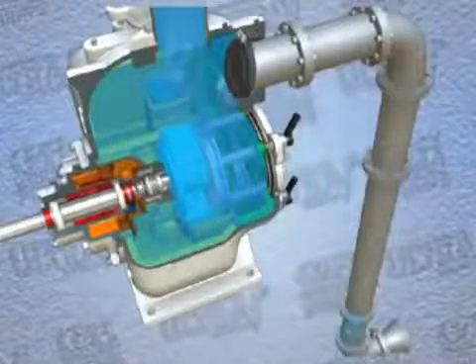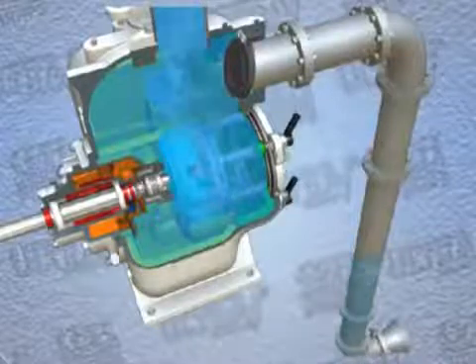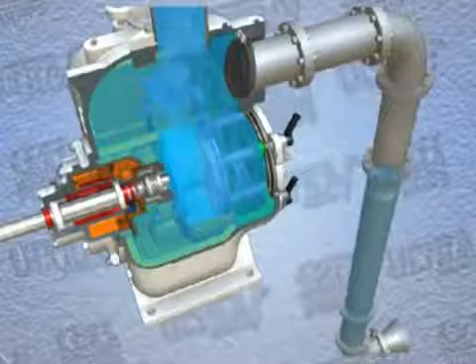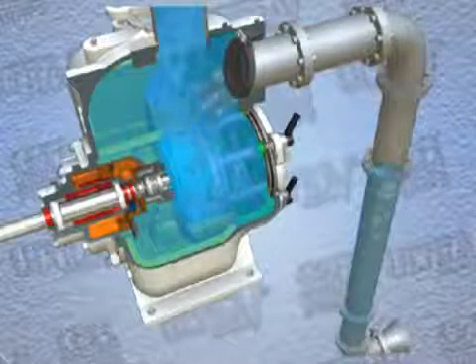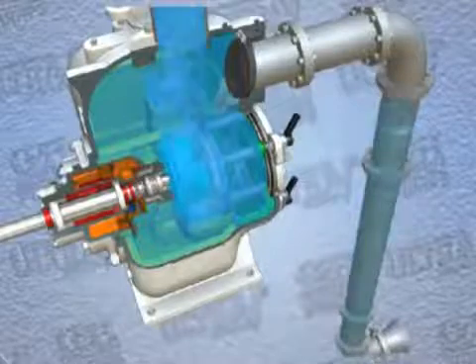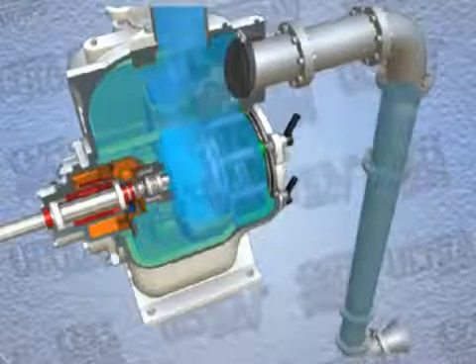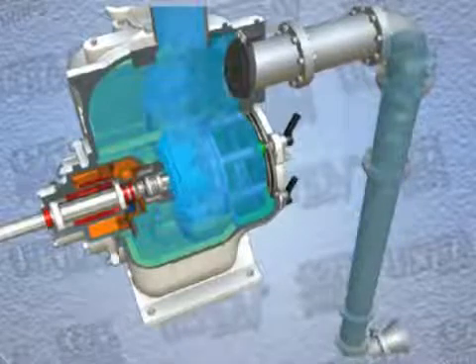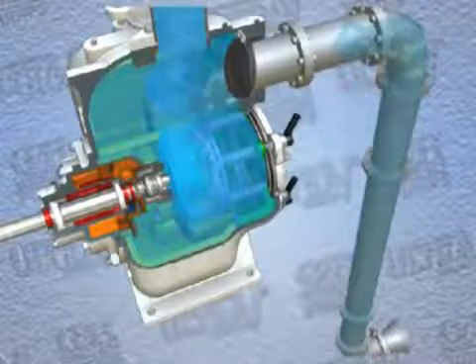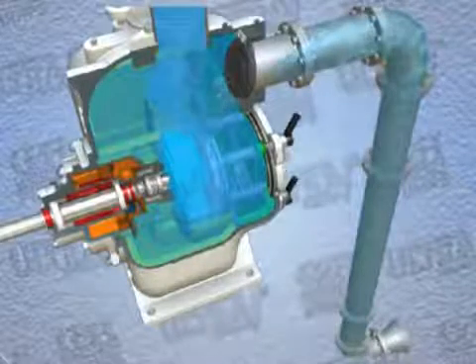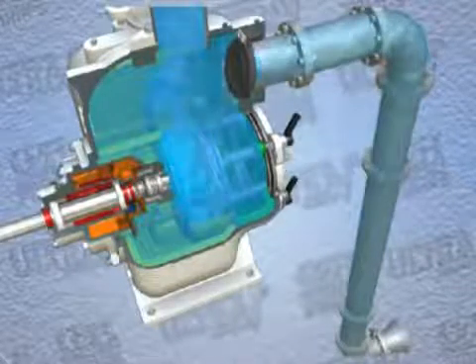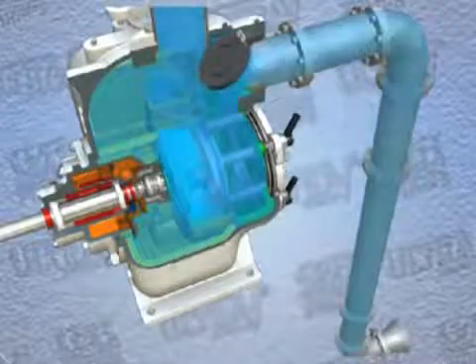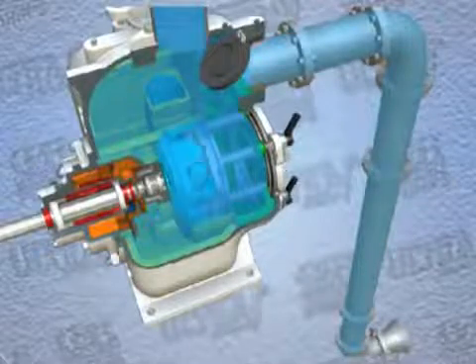After the initial prime, all Ultra V-Series pumps are designed to reprime automatically, even in a completely open system with a dry suction line and partially filled pump casing. The superior repriming capability is made possible by the unique design of the pump that allows for adequate liquid to be retained. Outstanding repriming capability, thanks in part to the internal volute casing design, means priming after the initial prime is automatic and extremely dependable. So much so that the Ultra V-Series remains self-priming even in an open system with a completely open suction line, and the pump can continue to reprime automatically even if the check valve is removed.